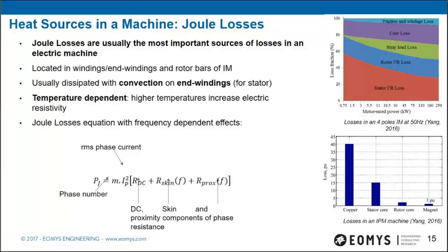Joule losses are usually the most important source of losses — for example, in a low-rated power motor they represent around 80% of total losses. They are located in windings or rotor bars for induction machines, and usually dissipated from the stator via convection on the end windings. They are very temperature dependent, since electric resistance increases with temperature. The Joule loss equation includes DC components on the left and frequency-dependent skin and proximity effect resistance terms on the right.